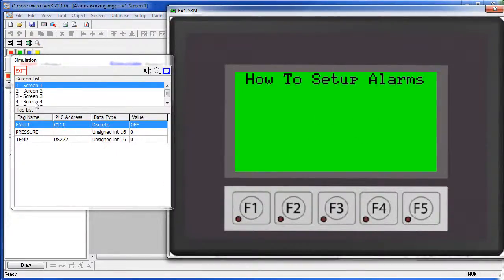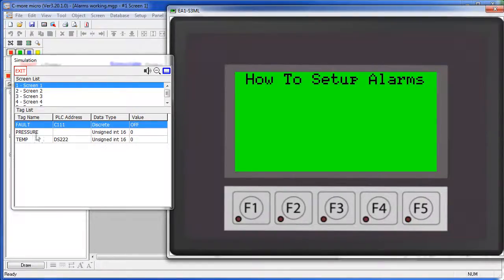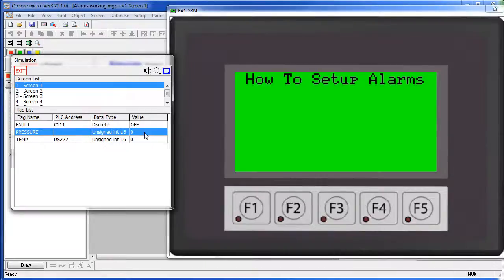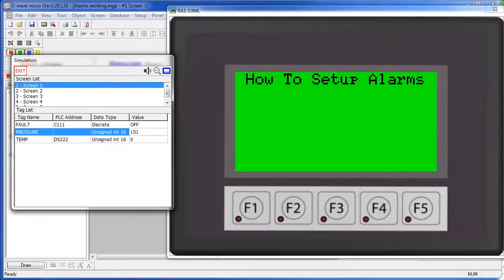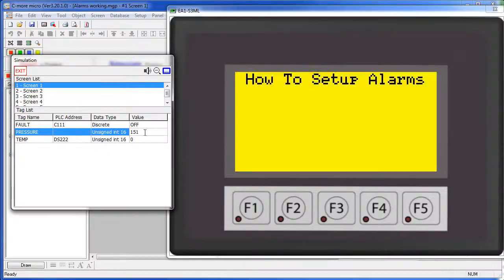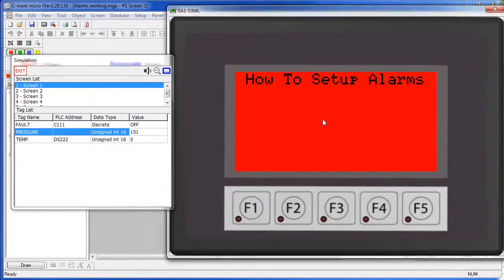Again, we have no controls here so we will just come over to our control window and force these alarms. So, let's see, when the pressure went above 150 psi – we are supposed to get an alarm so let's make it 151 – and sure enough we get our blinking screens and our beeps.